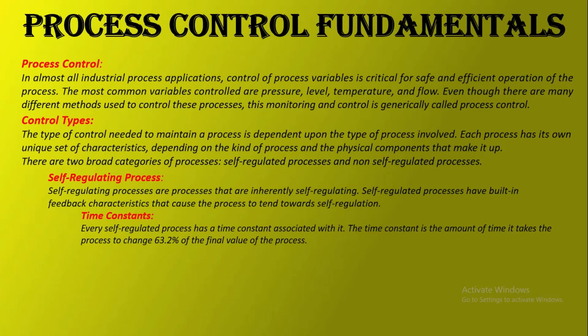In a self-regulating process, there is a time constant associated with it. The time constant is the amount of time it takes the process to change 63.2 percent of the final value of the process. In this example, if the process changes by 10 inches, the time it takes to change 6.32 inches — that is, 63.2 percent of 10 inches — is the time constant. It takes five time constants for the process to complete the total change.